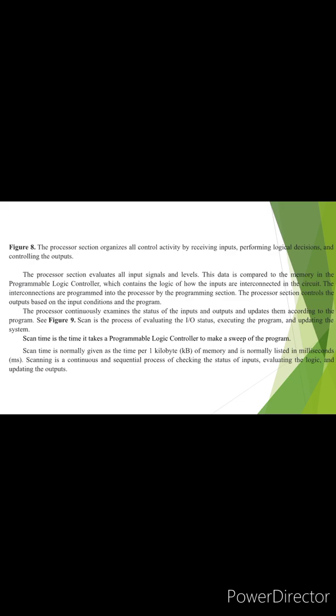Figure 8. The processor section organizes all control activity by receiving inputs, performing logical decisions, and controlling the outputs. The processor section evaluates all input signals and levels. This data is compared to the memory in the programmable logic controller, which contains the logic of how the inputs are interconnected in the circuit. The interconnections are programmed into the processor by the programming section. The processor section controls the output based on the input condition and the program. The processor continuously examines the status of the inputs and outputs and updates them according to the program.